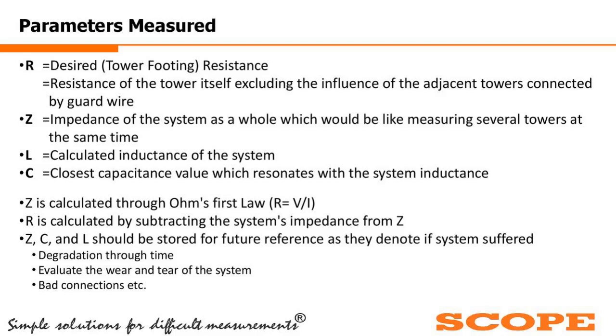And Z is calculated through Ohm's law, R equals V by I. R is calculated by subtracting the system's impedance from Z. Z, L and C should be stored for future reference, as they denote if the system has suffered any degradation over a period of time, or to evaluate the wear and tear of the system, if something has gone bad, those sort of things.